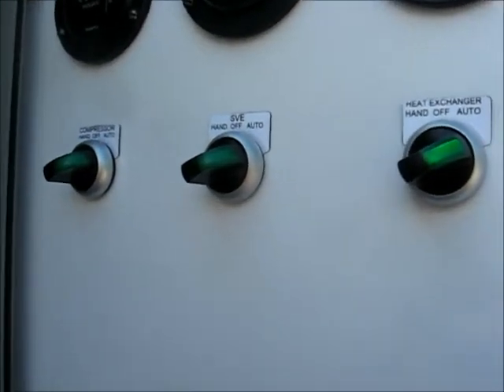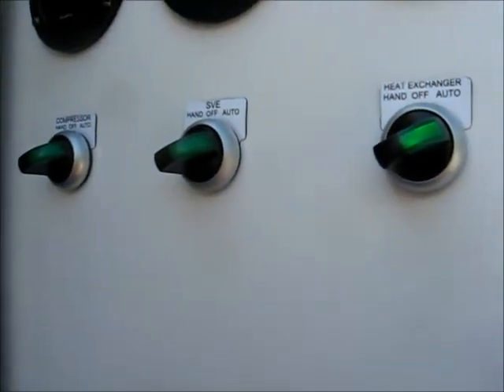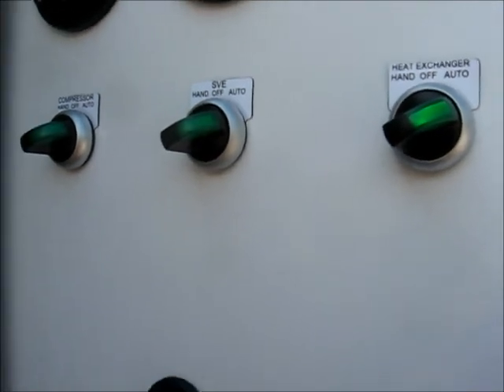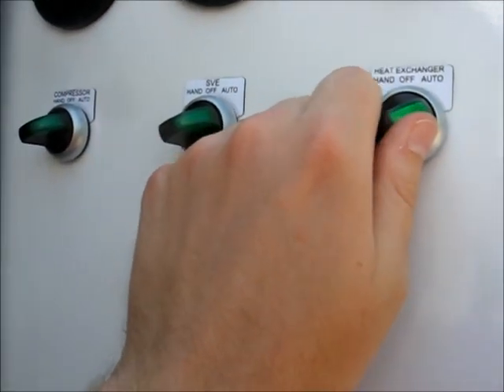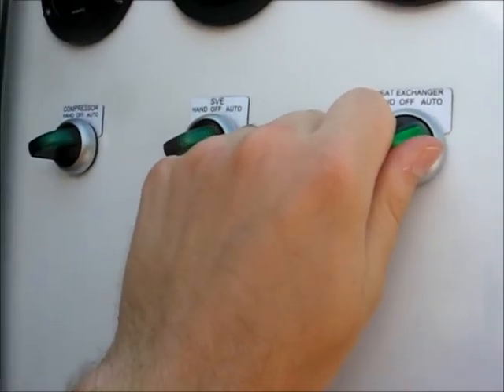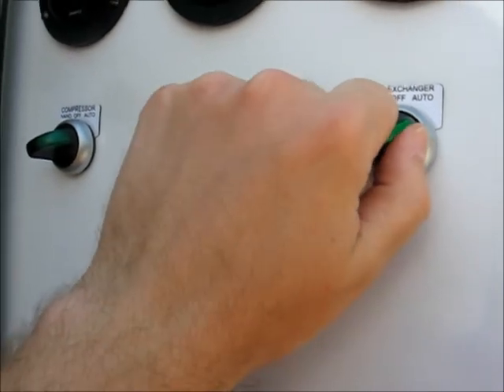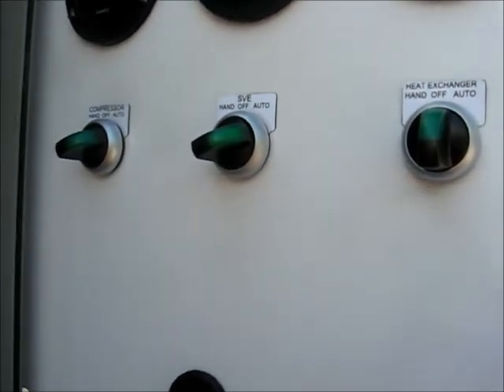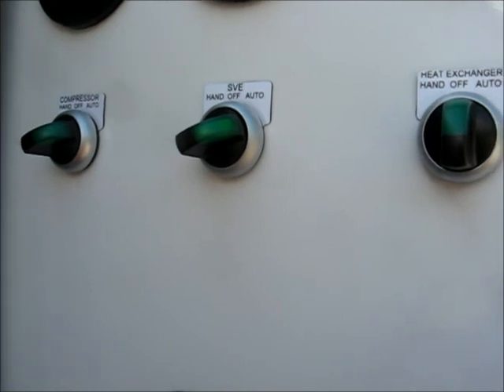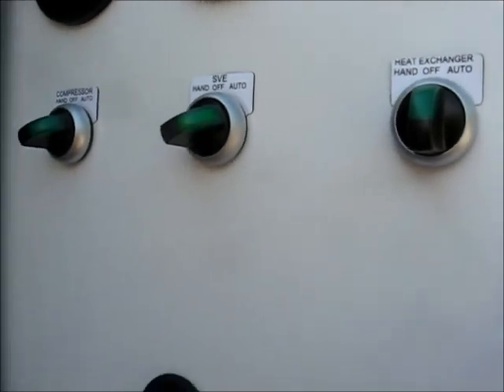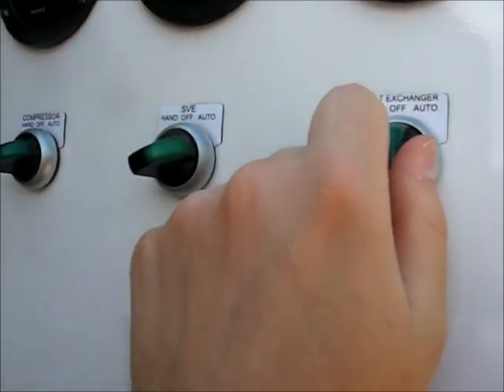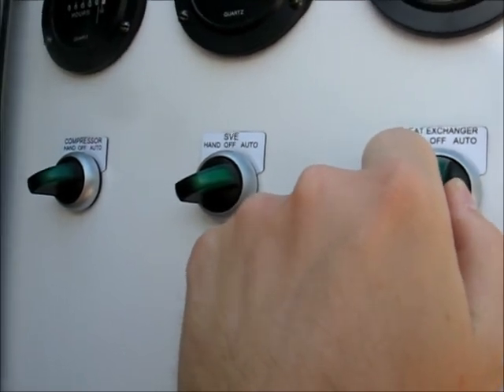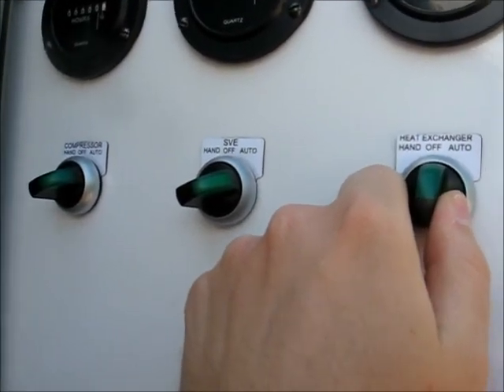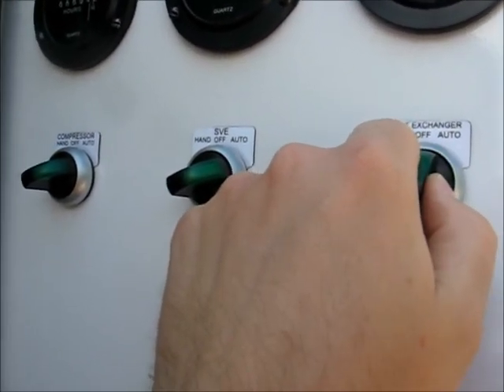The next thing we're going to do is show the interlocks. So right now everything is running. If we shut the heat exchanger off, the air compressor should turn down, or turn off. You can hear the air compressor's off, but the SVE is still running. Now if we turn this heat exchanger back on, they should both come back up, although the air compressor does have a bit of a time delay to prevent too much inrush.